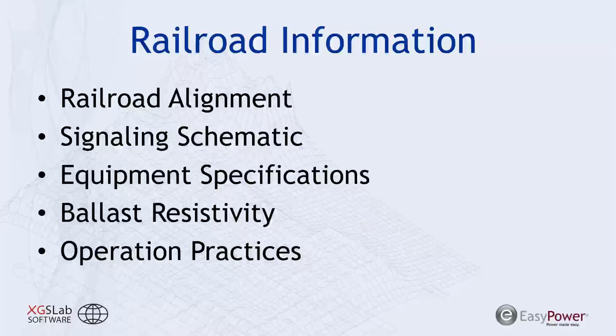In a railroad analysis, you'll need the railroad's alignment drawings and its signaling schematics to understand how track blocks are working and where that railroad is located in the world relative to the transmission line. Any equipment specifications are very useful in determining the 60 hertz limitations, or how robust it is against AC interference concerns. Any ballast resistivity measurements, railroads may have a limit that they operate with. It could be as little as 4 ohm k-foot. It could be as high as 50 ohm k-foot for newly installed material. And different operational practices of the railroad.